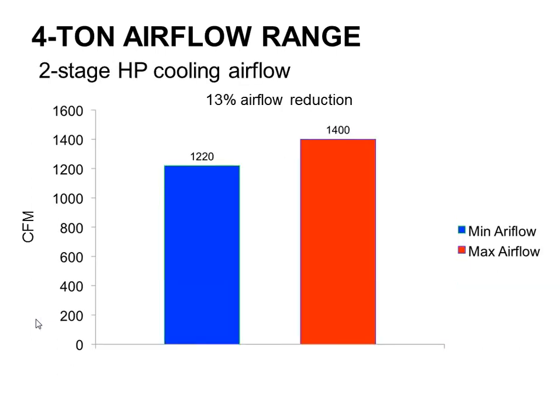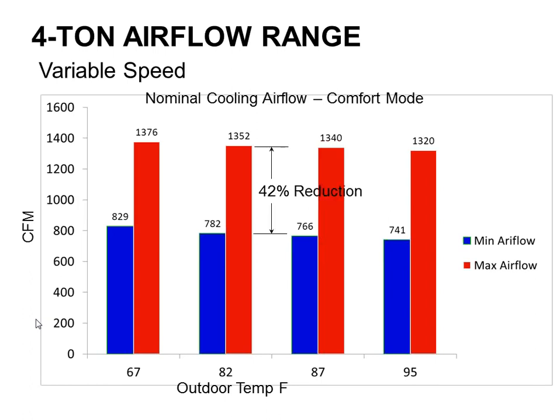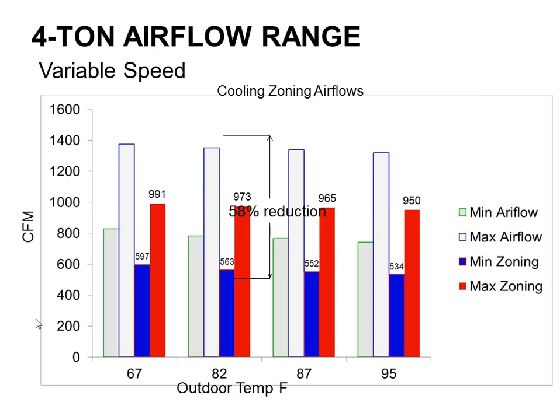Then here's a 4-ton example, right? Similar kind of scenario. Not quite as dramatic as the 3-ton unit, but still, normally I'd only be able to cut back the speed about 15%. Now I'm going to be able to cut it back about 40% with the variable speed unit. If I put the variable speed unit on a zoning system, I can cut them back about 60%. Now, with that being said, these condensing units / heat pumps have to be combined with those Infinity and Evolution furnaces and fan coils, and they have to be operated by one of the Evolution or Infinity wall controllers. You cannot use them with a regular thermostat.